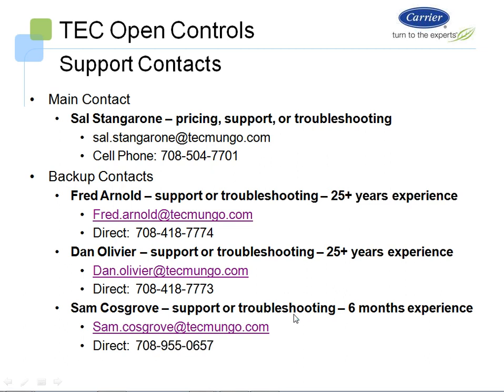Jim's question: if our chillers and RTUs are CCN native, do we still need a BACnet card to get the points through if the RTU is specified open? Yes, you do need a BACnet card on a CCN controlled unit to communicate with any open product or BACnet product. So even if you have a specified rooftop unit that is open, you'll have a BACnet card, but if you want to talk with a chiller or other rooftops that are CCN native using carrier's standard proprietary protocol, you will need a BACnet card or translator card, because CCN is not standard BACnet. Hopefully that answers your question, Jim. If you want to discuss in more detail, give me a call, or if anyone else has questions, please feel free to reach out for any help you'd need.